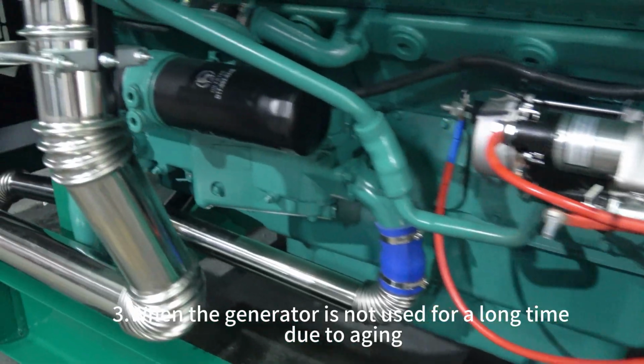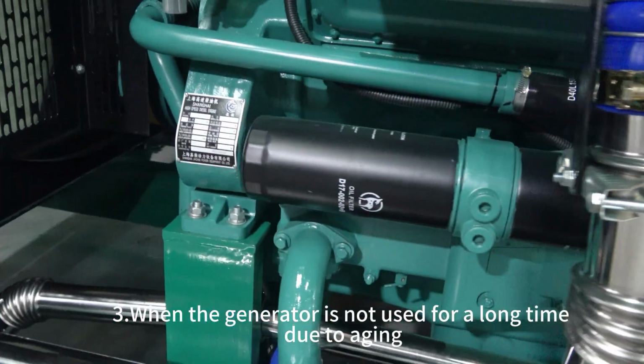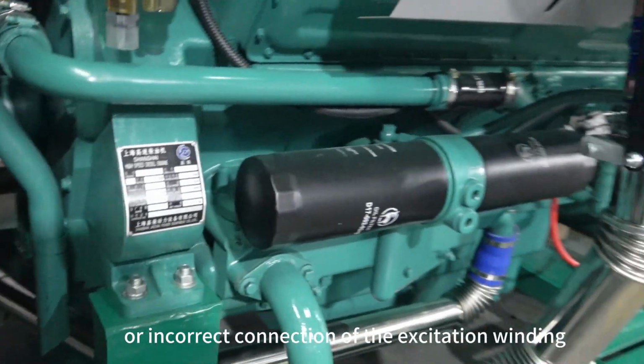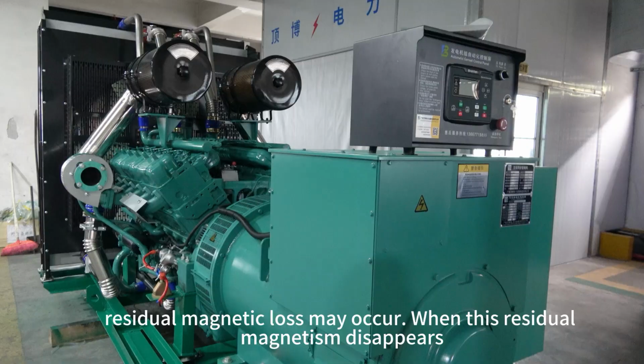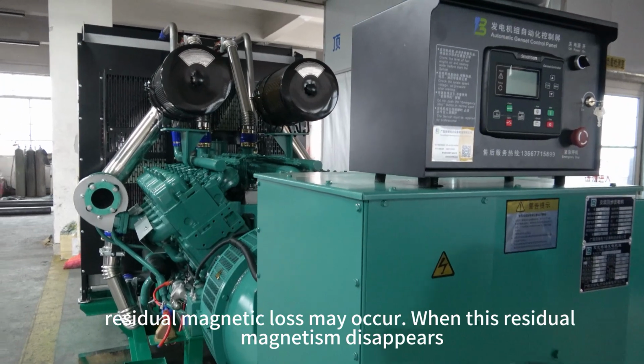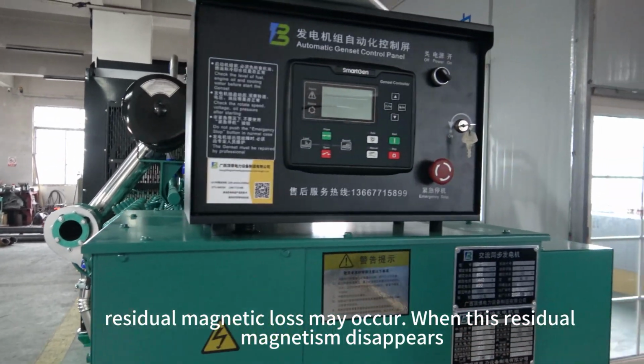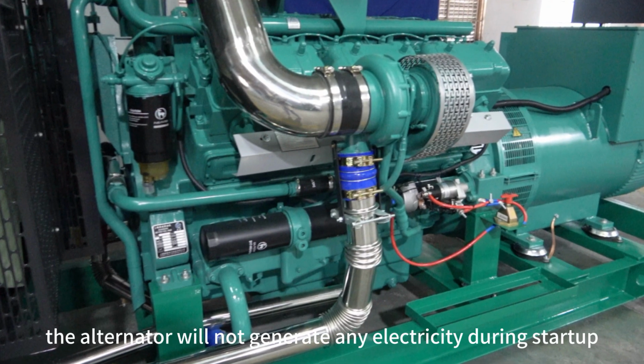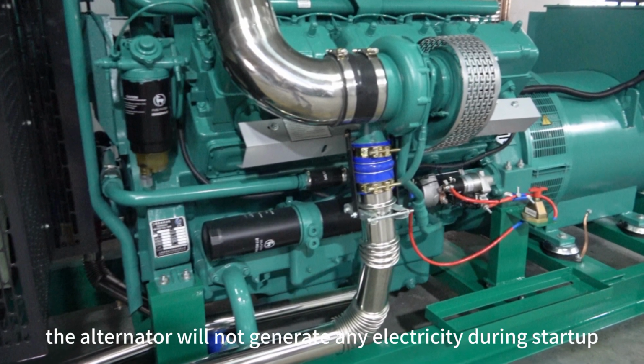When the generator is not used for a long time, due to aging or incorrect connection of the excitation winding, residual magnetic loss may occur. When this residual magnetism disappears, the alternator will not generate any electricity during startup.